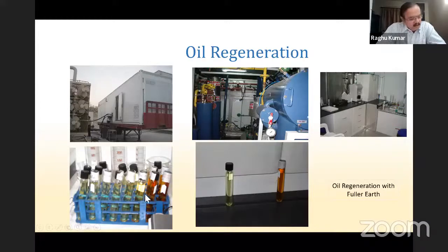These are the set of oil samples which have been taken during the process. You can see the change in colors. This was the initial oil color, and this is the final oil color. The advantage of this is that the whole process is carried out while the transformer is live. We switch it off only one time for connecting the hoses and a second time for removing the hoses. And the oil circulation goes on continuously on a live transformer.